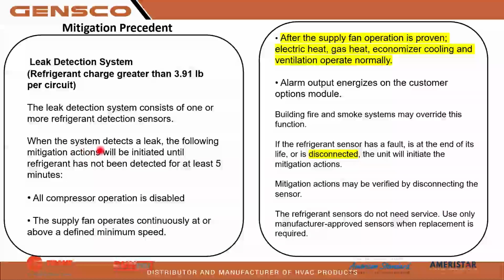When the system detects a leak, the following mitigation actions will be initiated until refrigerant has not been detected for at least 5 minutes. So all compressor operations are disabled. If it senses a leak, it's going to disable the compressor. The supply fan operates continuously at or above defined minimum speed. So it has been ramping up about 50% of the capability of the tonnage size. After the supply fan operation is proven, electric heat, gas heat, economizer cooling, and ventilation operate normally.